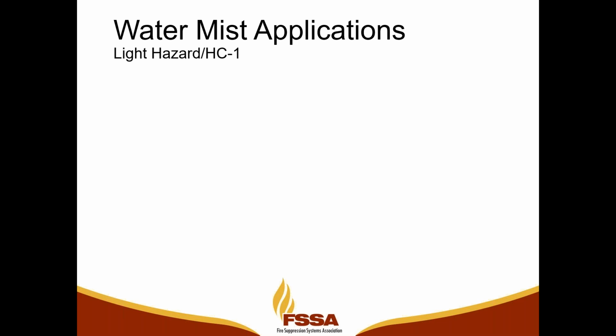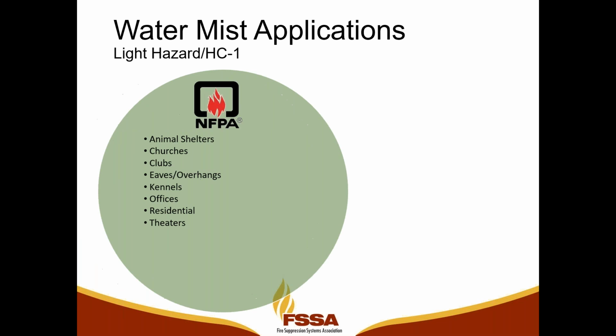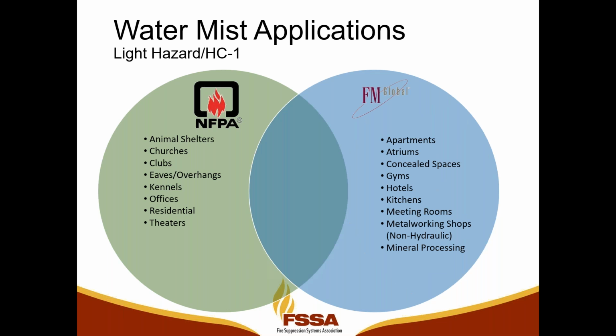Next slide. I want to talk a little bit about light hazard versus hazard category 1. So go ahead and click. If you look at NFPA's definition of light hazard, you're going to see these types of hazards specifically listed as defining light hazard. Next, click. And then if you look at FM datasheet 3-26, where they define hazard category 1, you're going to see these very specific words used to define that hazard. Next, click. And if you look at both of these, NFPA 13 and FM, you're going to see that they use this list of words in the middle where the circles intersect. They both use those words.